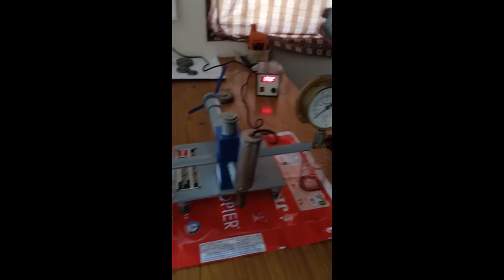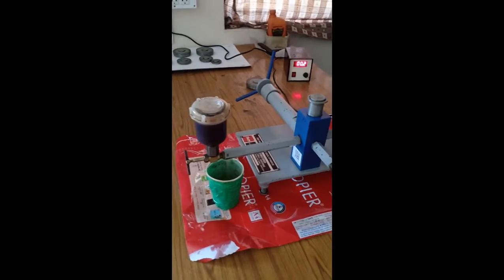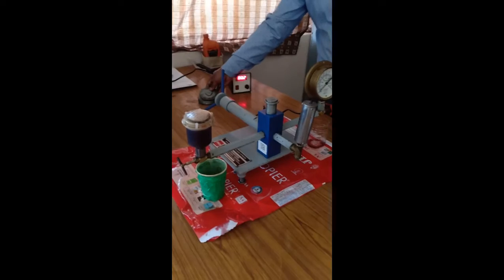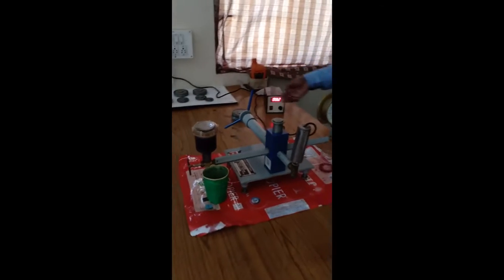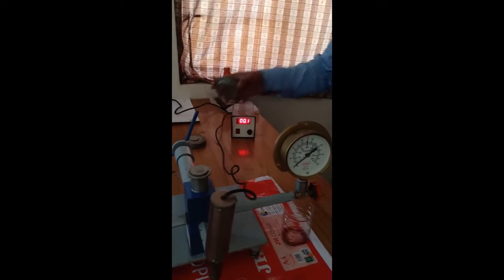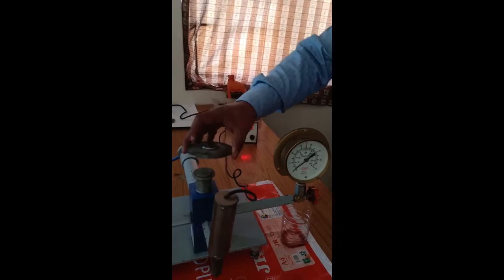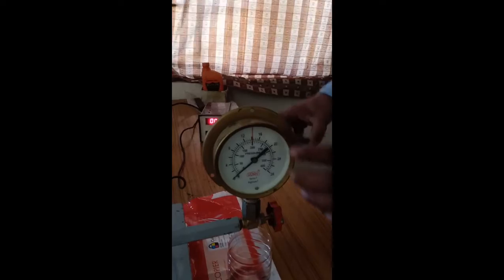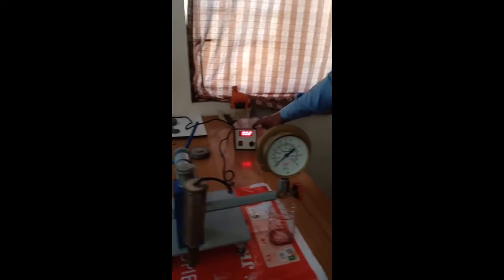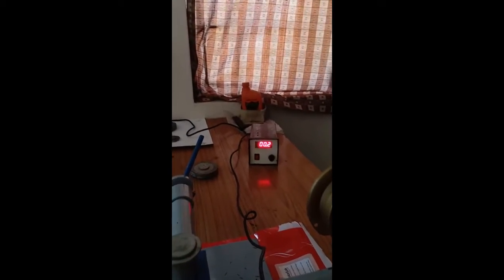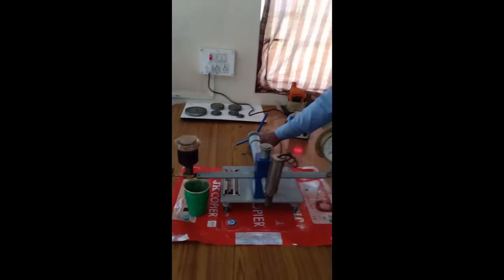We are checking whether the equipment is running properly. Initially, the equipment required is a pressure gauge, dead weights, and load cells. I am going to compare the dead weights by applying the load on this pressure gauge. This pressure gauge is used to take the pressure for different weights, and it indicates the value when I apply the load on this particular pressure gauge. Initially, we first need to set this to a null position, that is, the 0 position.